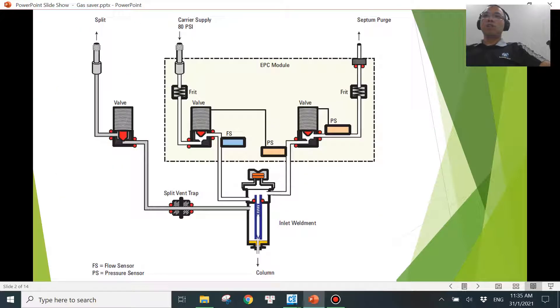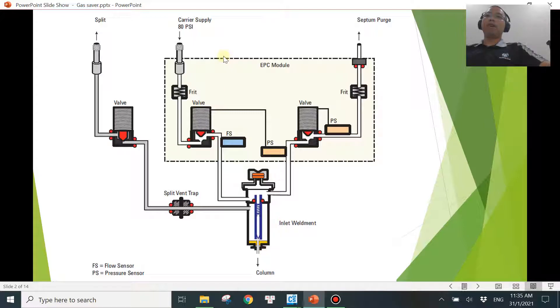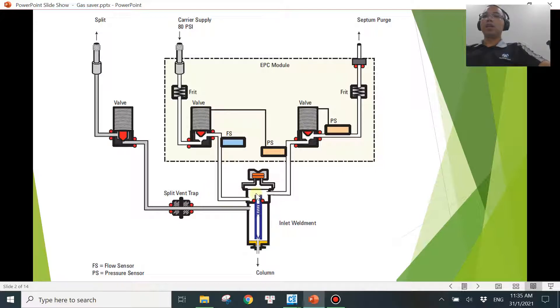Let me show you a schematic of the split/splitless inlet, where you have the inlet and the EPC Module on top. By the way, this picture is taken from the advanced operation manual from Agilent, which you can find on your PC when you install the software. Whatever carrier gas you supply into the inlet, we call it total flow. The total flow is split into three different flows: septum flow, split flow, and column flow. So total flow is a combination of those three flows — keep that in mind as we walk through the calculations.